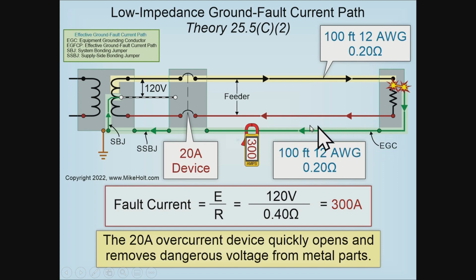Let's say we're running a 12 gauge wire back over to the source, and it's 100 feet. Well, if it's 2 ohms per 1,000 feet, 100 feet is 0.2, so we know we have fault current going out at 0.2 ohms and returning back to the source at 0.2 ohms. Using Ohm's law, I is equal to E over R. Oh, Mario, we need to change this R to Z, because we're in alternating current. So I is equal to E over Z, and it's in ohms. 120 divided by 0.4 is 300 amps.